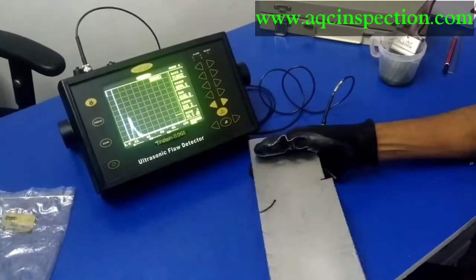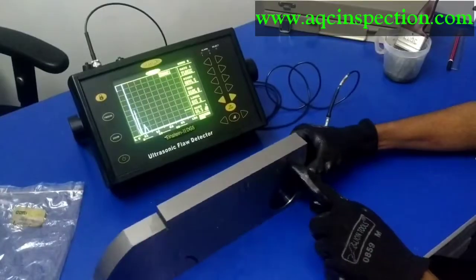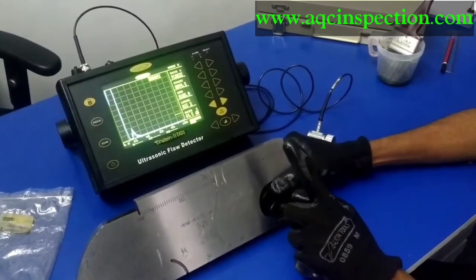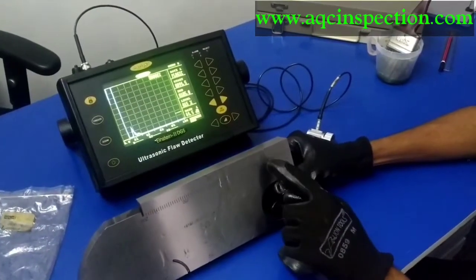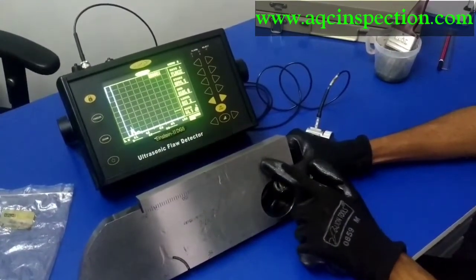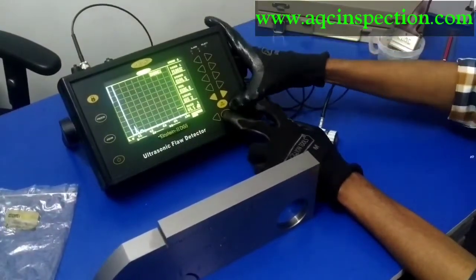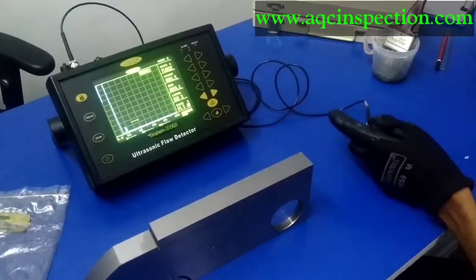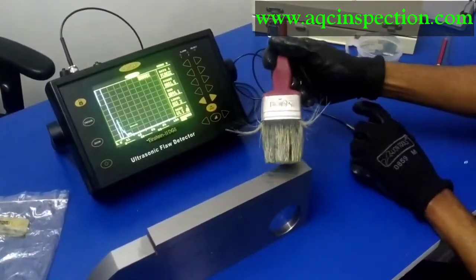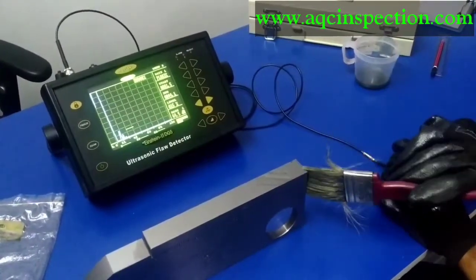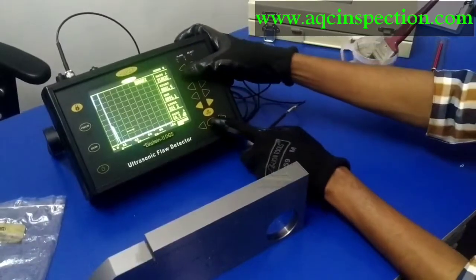And right now I am going to perform another one which is called a sensitivity calibration using this side drill hole right here. I have to catch this hole. I have to catch this hole to check whether I am getting 15 mm from the top and from here 35 mm. If I am getting it, then probe is sensitive enough for calibration or inspection process. I need a little more couplant here and on the side as well.